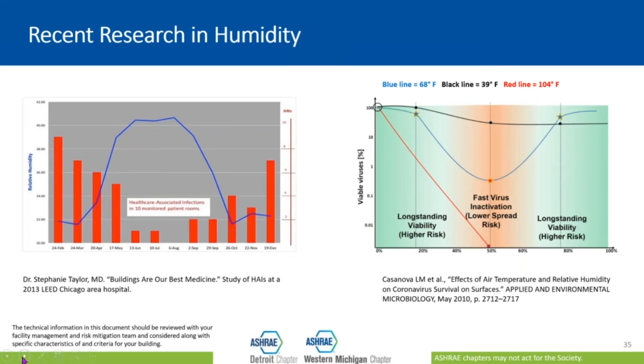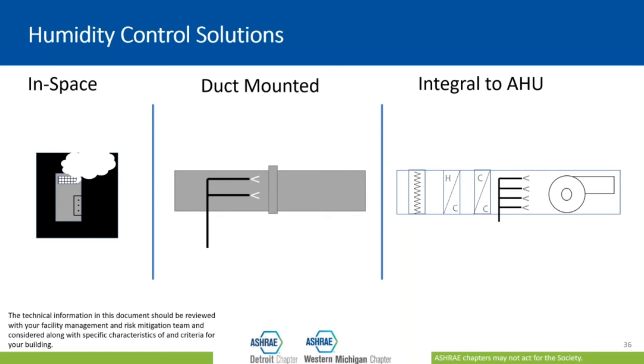So even though, and I'm not sure how things are done in Athens or in Greece, in Michigan, most buildings are not humidified. It takes a special building. It's either a library or a museum or a hospital, someplace where the application actually calls for humidification. Your average building here in Michigan is not humidified, and so this is something that would have to be added to systems. It could be added in the existing air handler, if there's space. Otherwise, possibly in the ductwork. A lot of buildings here in Michigan have boiler systems that do not have ductwork, and so we would be looking at in-space applications.